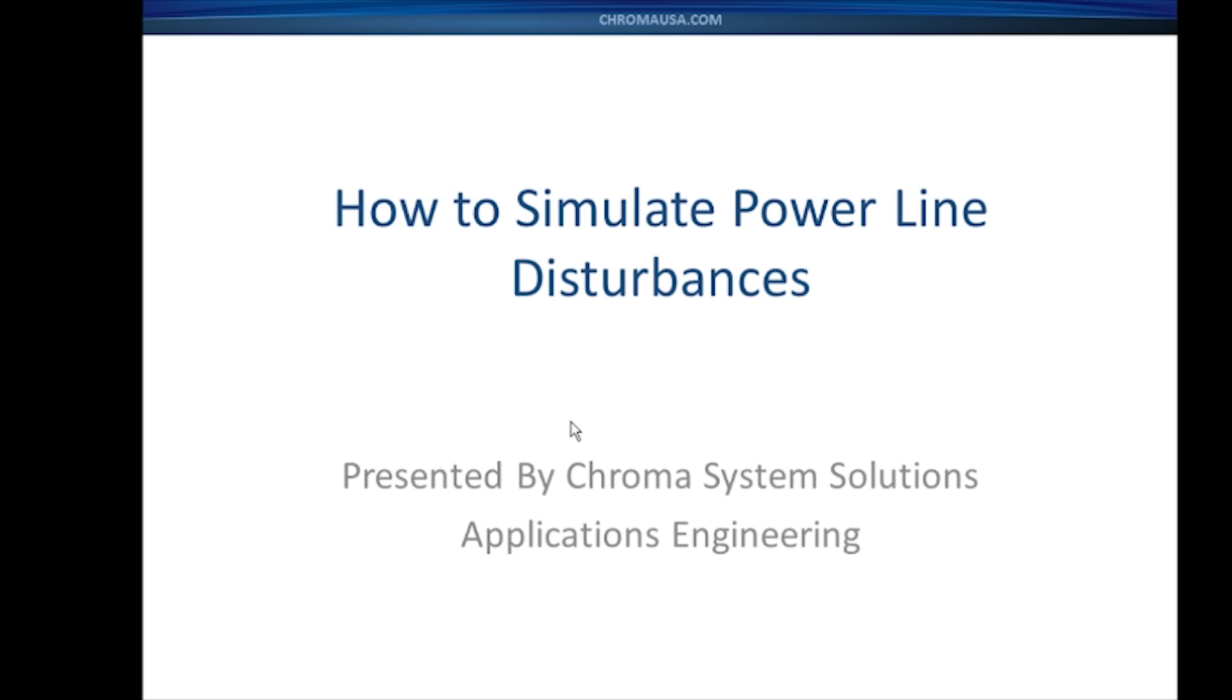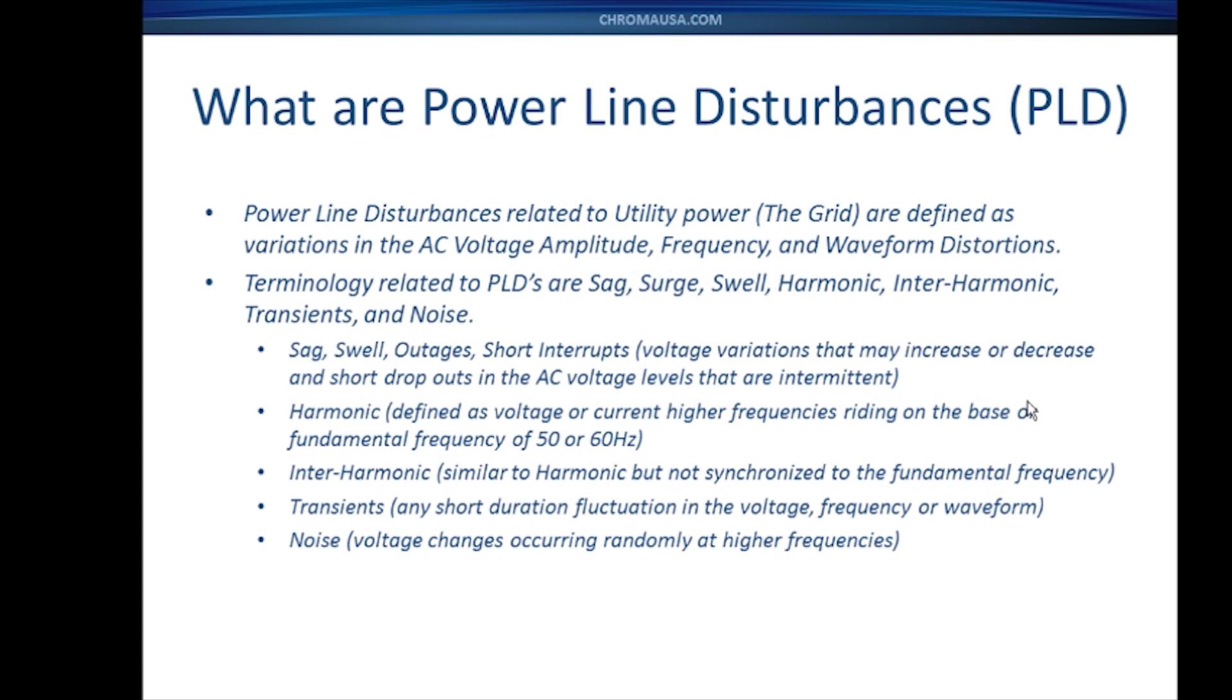Power line disturbances are defined as any variation in the AC voltage, whether it's in the amplitude of the voltage, in a variation in the frequency, or even the waveform itself. Power line disturbances also have related terminologies such as sag and surge, harmonic, interharmonic, transients, and noise.